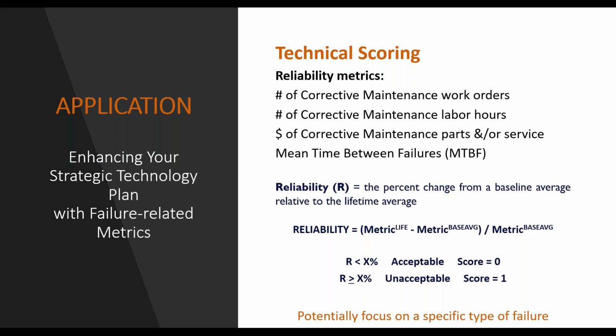So think about, again, back to what type of equipment. Do I want to set a general baseline for everything? Do I want to set a baseline that's just for imaging and a different one that's just for general biomed and something different for lab? Do I have a particular device, like that cancer planning system, that needs its own specific baseline? Is that baseline the first 3 years, the first 5 years? Some folks say, well, that's the burn-in time. I'm going to see the best and worst of this thing in the first 3 years, and I want to use that as my baseline. Others say, no, I need that burn-in time, and then my best baseline is actually the next 3 years.